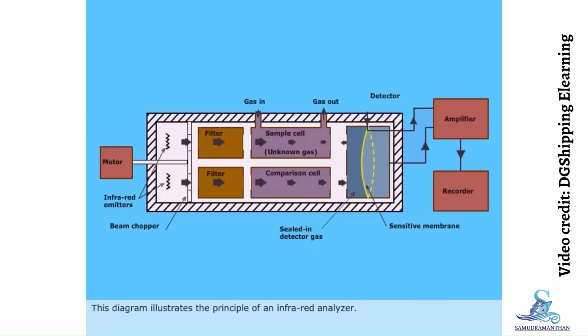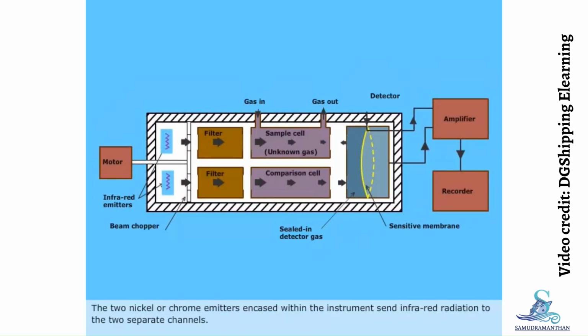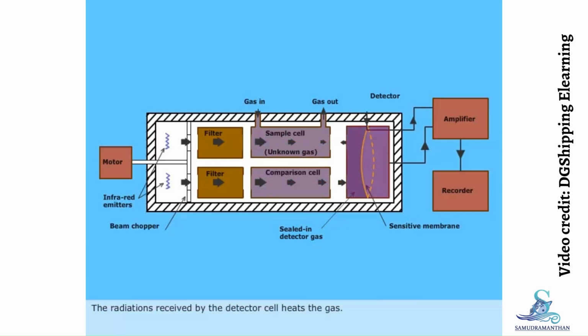This diagram illustrates the principle of an infrared analyzer. This multipoint instrument employs the property of hydrocarbon gas to absorb infrared radiation. The two nickel or chrome emitters encased within the instrument send infrared radiation to two separate channels. Infrared radiations are sent through a reference cell free of hydrocarbons and a sample cell. A semicircular beam chopper driven by an electric motor alternately blocks the two channels. The radiations transmitted from the channels pass through the detector cell. The radiations received by the detector cell heat the gas. The sensitive membrane of a condenser microphone detects the resultant rise in pressure.